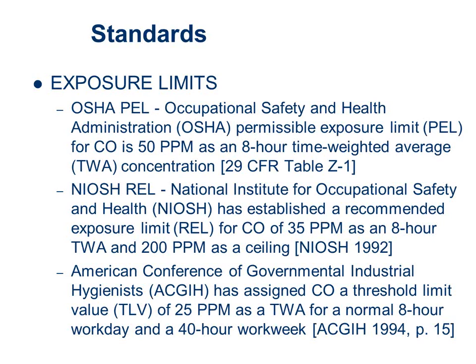But for most of what we do—vehicle spaces, car dealerships, parking garages, boiler rooms, these kinds of things that have carbon monoxide—if I have 25 parts per million, something's not right. Something's not working correctly: my exhaust system's broke, or my heat exchanger's cracked, or something bad has happened. So I don't need to wait till I get to 50 before I freak out. I'm going to freak out at 25. That's the way I look at it, at least in terms of carbon monoxide—let's go with the more conservative one, 25 parts per million.